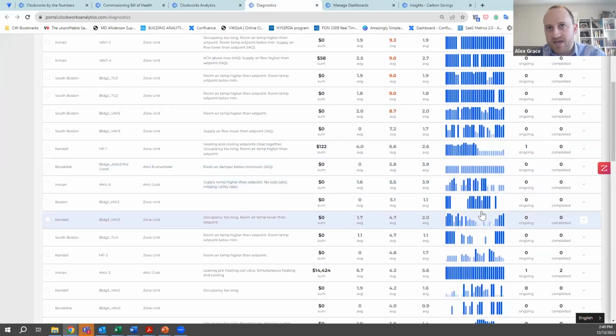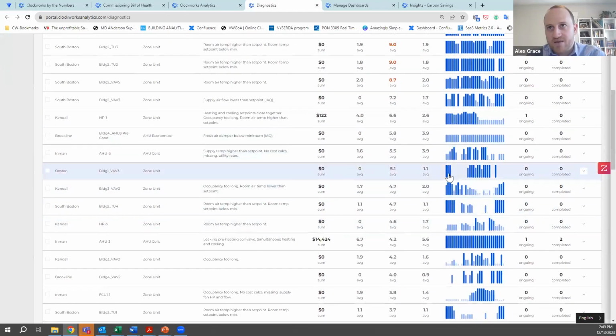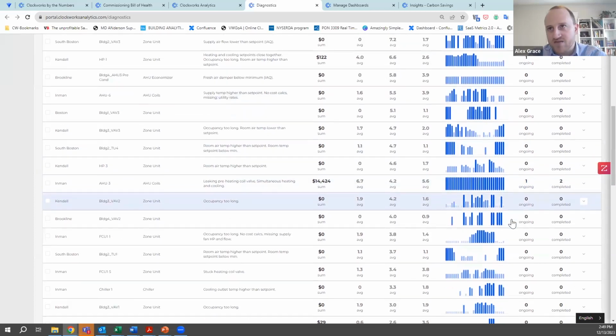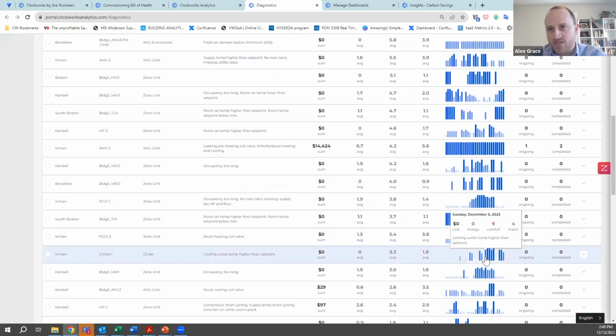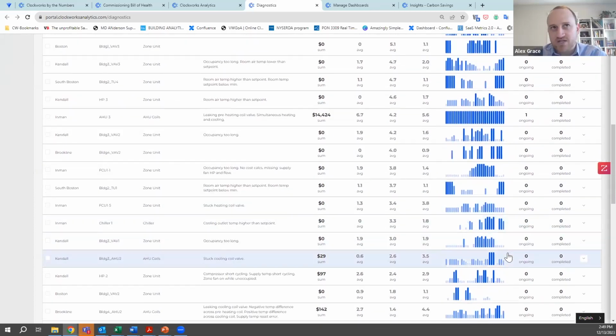So it could very well be the case that the problem was happening and then it wasn't, and then it came back. Supply airflow was too low here, but was good on these other days. Now, why was it intermittent? Could be a range of reasons. Maybe it's only happening on weekends, or maybe during certain outdoor weather conditions and not others. You can see the amount of variability in these charts, which tells us that doing commissioning on a snapshot of time is really not enough.